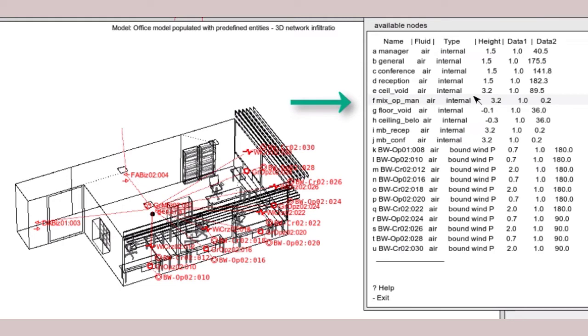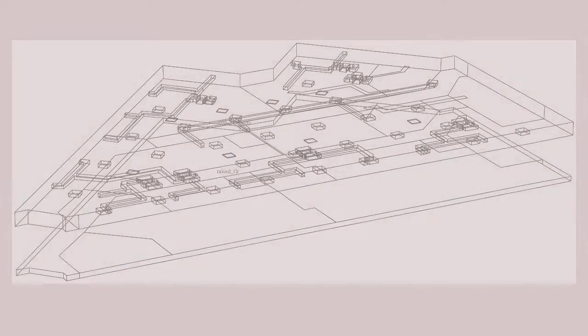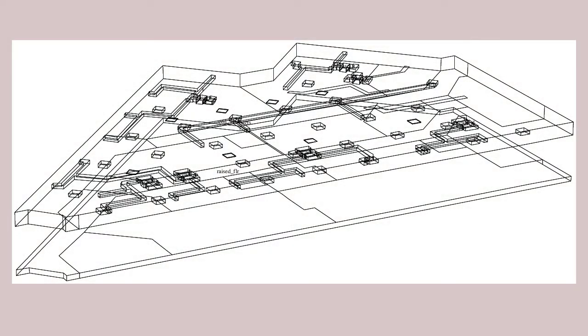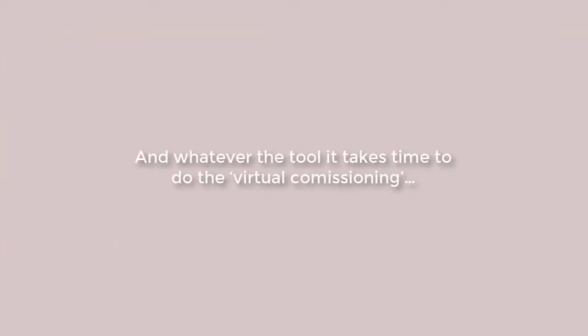Of course, at this stage, the model is not attempting to do duct design. If I was rather more concerned about what was happening in the ceiling void, say the impact of poorly lagged ductwork, I could up the model resolution and treat the ductwork itself as a series of thermal zones. And although I have used such approaches many times, there's still the need to dial in the capacities, flow rates, and tune the flow and mixing box controls. That takes time.